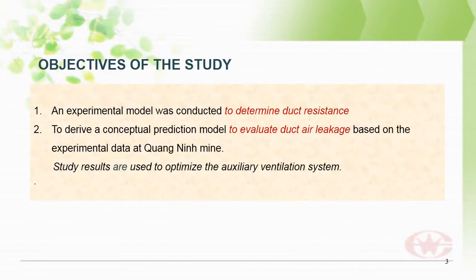Object of study: an experimental model was constructed to determine duct resistance, and a conceptual prediction model was derived to evaluate the duct air leakage based on the experimental data at Quang Ninh mines. Study results have been used to optimize the auxiliary ventilation system.